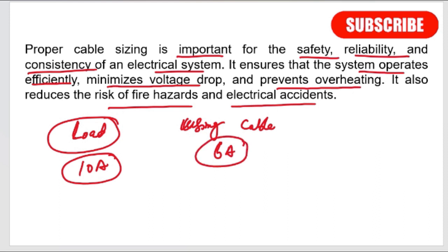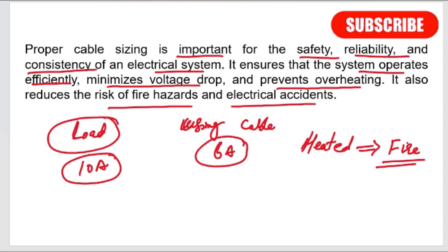whose current rating is only 6 amperes. The load is drawing 10 amperes but the cable is only rated for 6 amperes. Due to overloading, the cable gets heated and there is a chance it will catch fire, causing an electrical accident. Additionally, if the resistance of the cable is very large, there will be a large voltage drop — the load will not get proper voltage, will not function properly, and its efficiency will decrease. To avoid fire risk and to increase efficiency, the cable size must be proper.